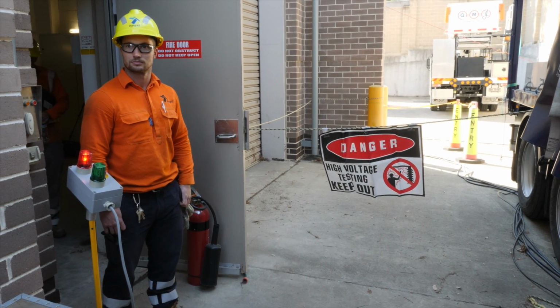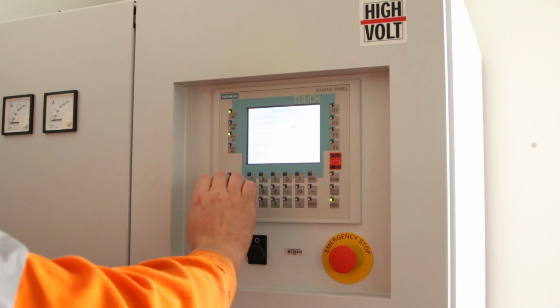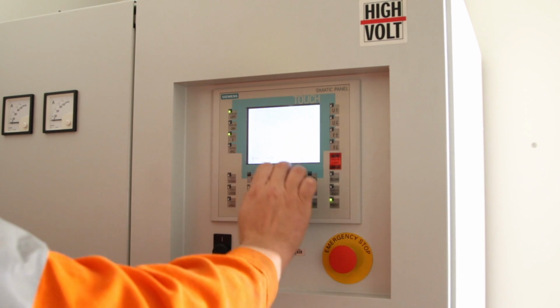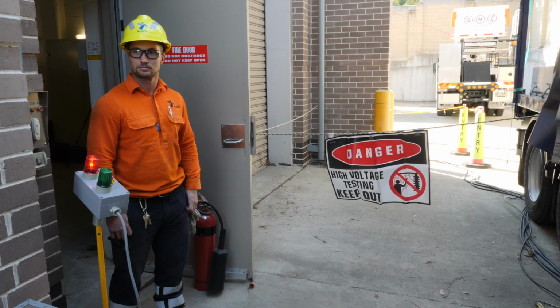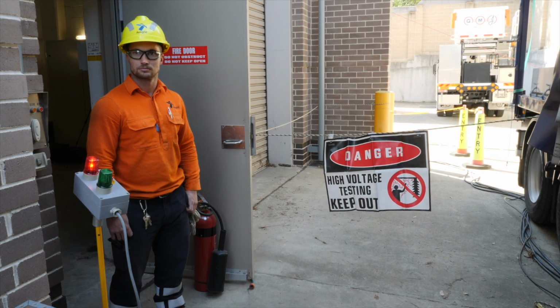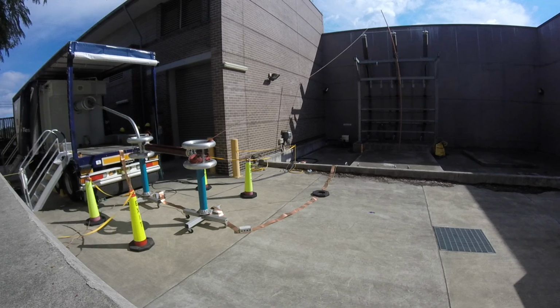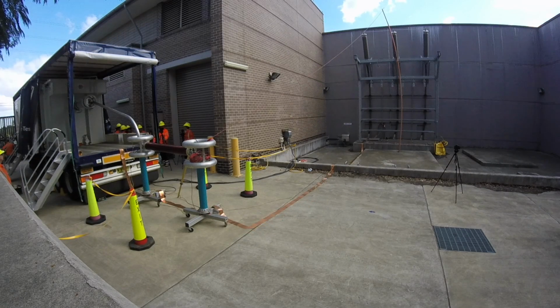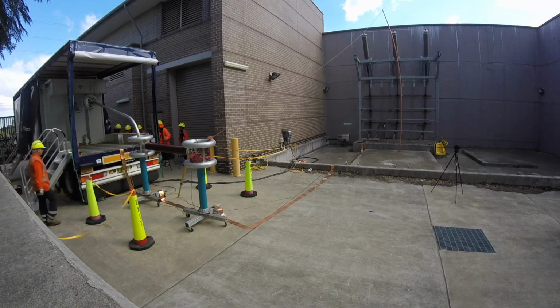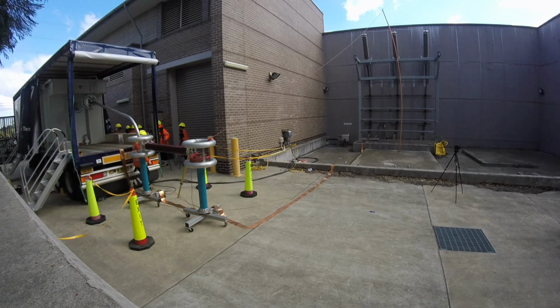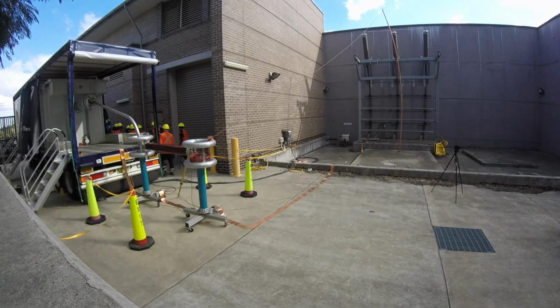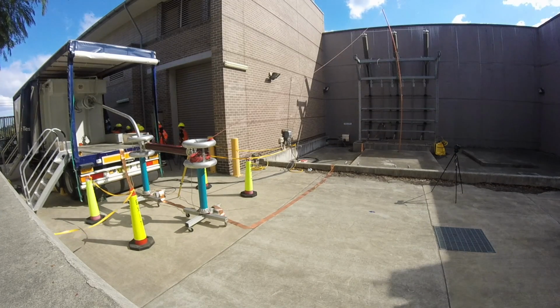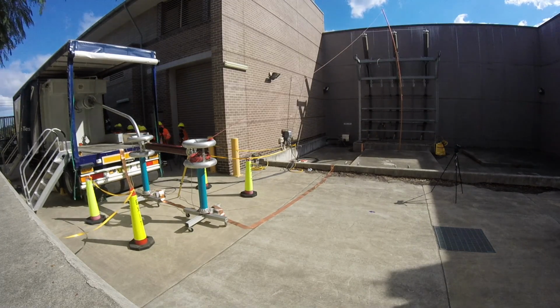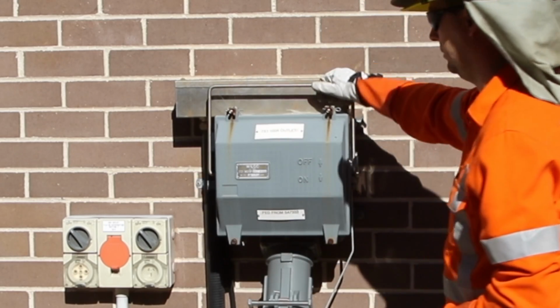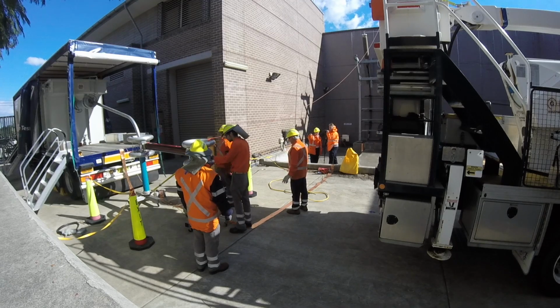The testing is now in progress and is being monitored by the testing engineering officers inside the control cabin of the test trailer, and the area is being watched by safety observers. Once the testing is complete, the tester in charge will announce that the test set is down and off, and then a manual earth will be applied to the test trailer output as a visual indication that the test circuit is earthed. The power is cut and the pack-up begins. Everything remains earthed and the equipment is packed away. Then we turn off supply, and as a final step, the earthing is detached and also packed away.